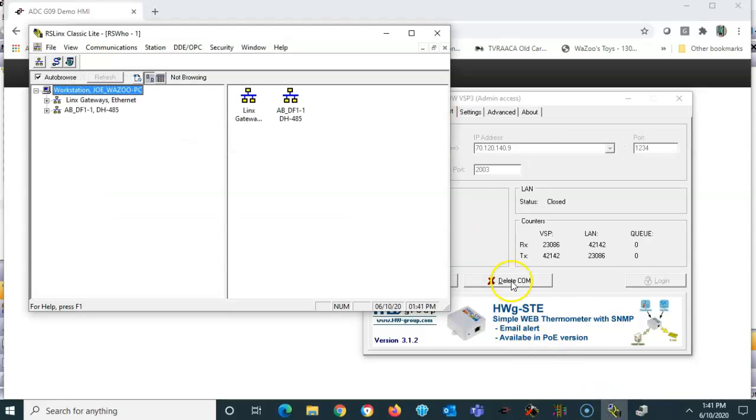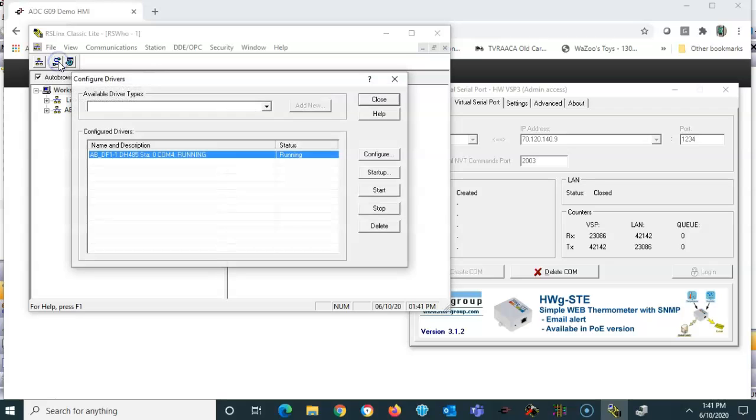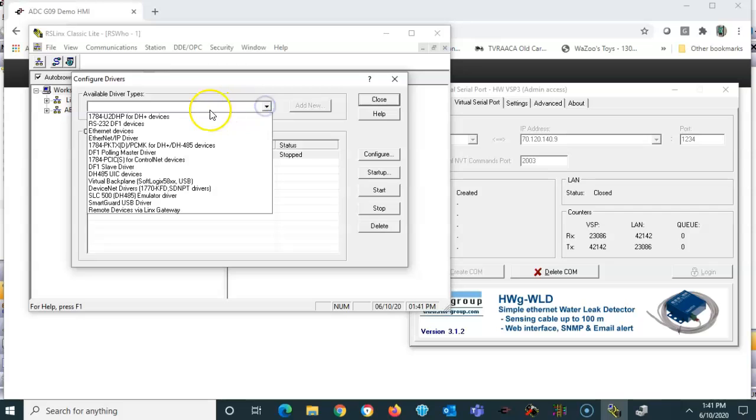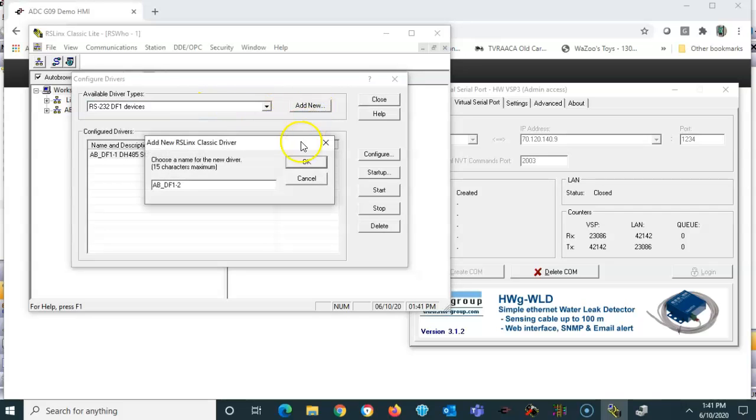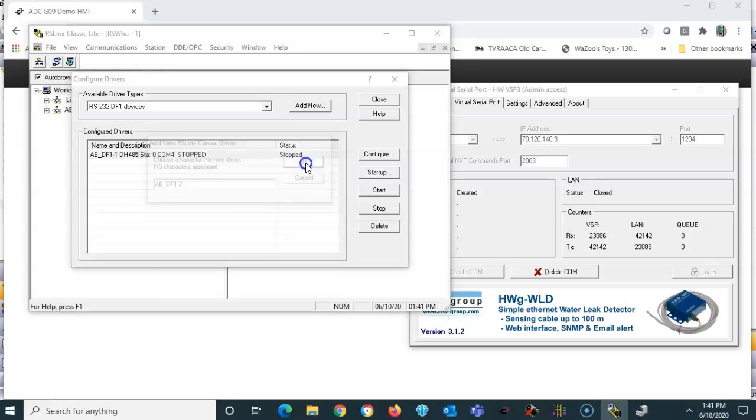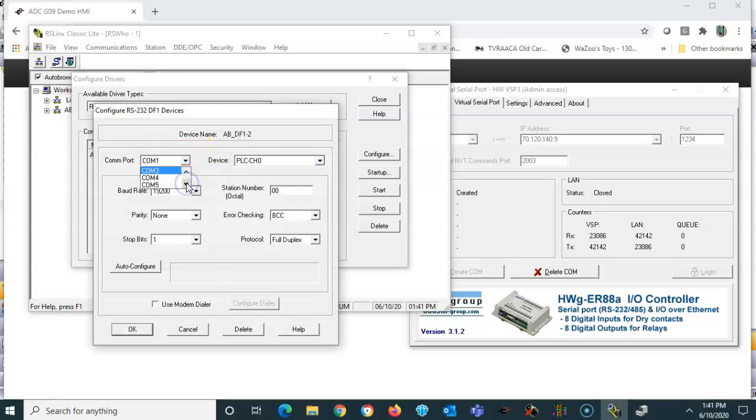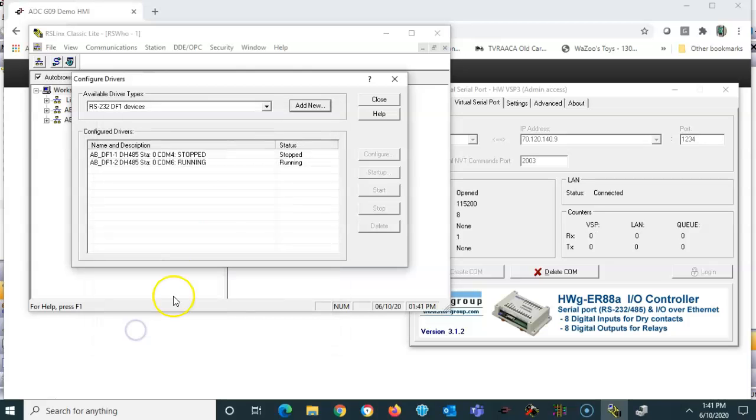So then I'll go back to RSLinx here, and I want to remind you here I'm using COM6. So in RSLinx, I'm going to go here. I'm going to add another one. Maybe I'll stop this one, not that it matters. I'll hit the pull-down, I'll choose again RS-232. This is going to sound really weird, but when I click OK, hit the pull-down here, I'm going to choose COM6 this time right here, and I'm going to hit auto-configure. And let's see, you look over here you can see some stuff, and it says auto-configure successful. Good.